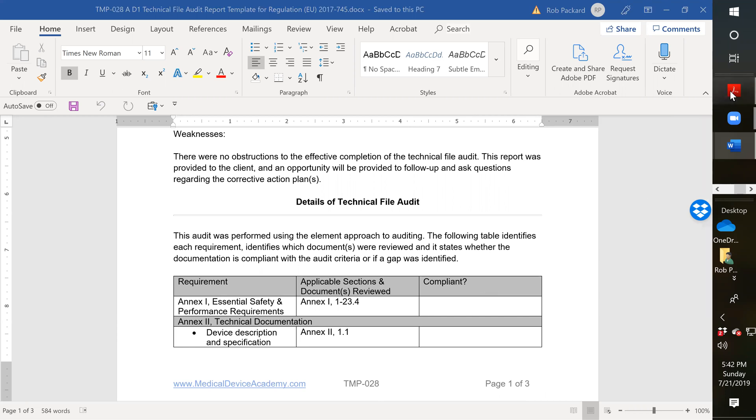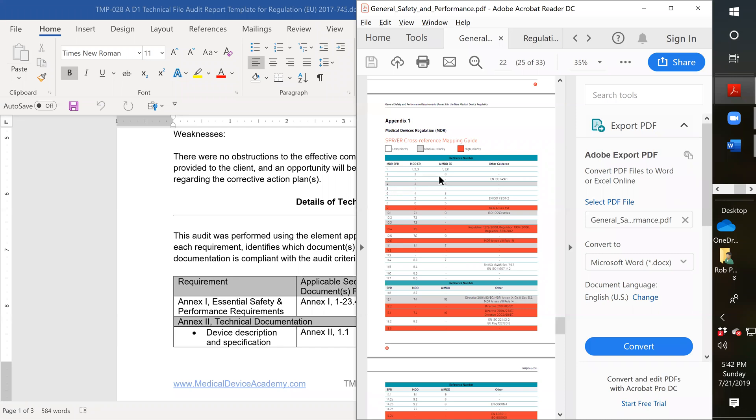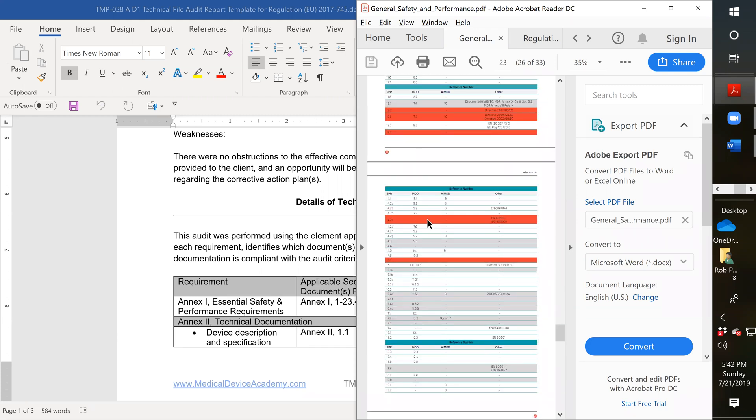So one of the tools that I found, BSI has actually done a cross-reference map. When I go through this training on the webinar, I'm going to actually point out what you want to look for in the different places where they're different. They've indicated here is what's in the new MDR, here's what's in the MDD, here's what the AIMD, here's other guidance to look at. And then they indicate where there's gaps. So this is what the new MDR has, but this is where there was a gap in the MDD that now has to be filled. So you might look at what did they put in for section number three, section number nine, section 10.6, 11.2, and 11.3. The list goes on for several pages.